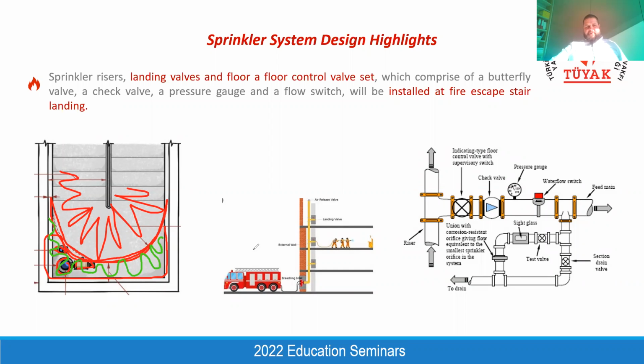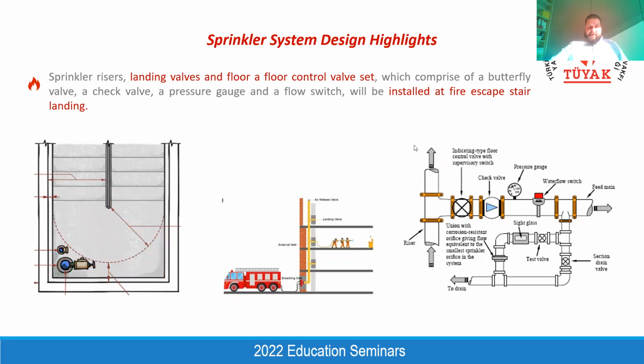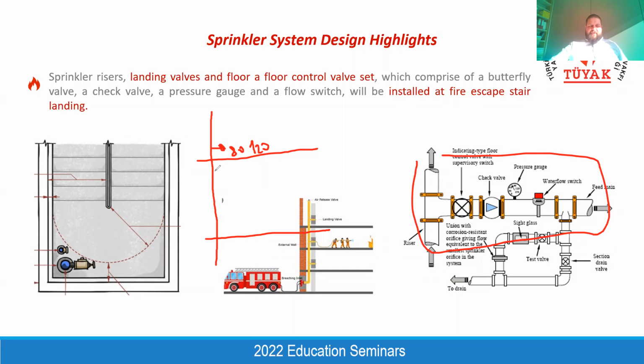Just for your information, I will check the next slide. When we see the section, for example, this is one floor and this is the other floor of the staircase, with the riser going through the upper floors. These landing valves are located about 80 centimeters to 120 centimeters from the floor level. But these gate valve groups are located near the ceiling. We have a gate valve here, and we have a flow switch and pressure gauge.